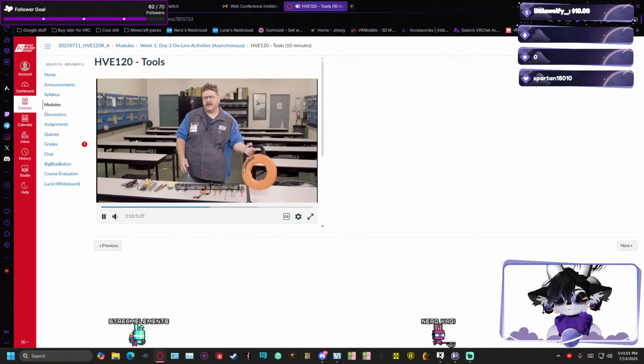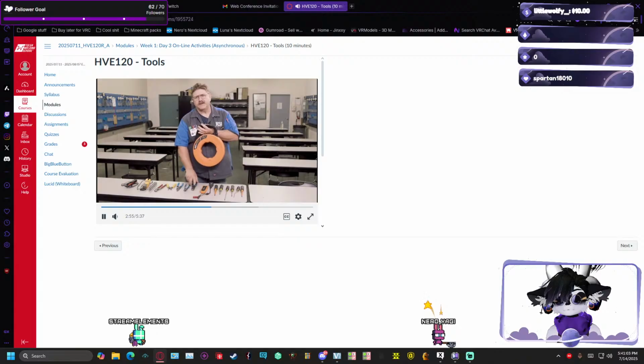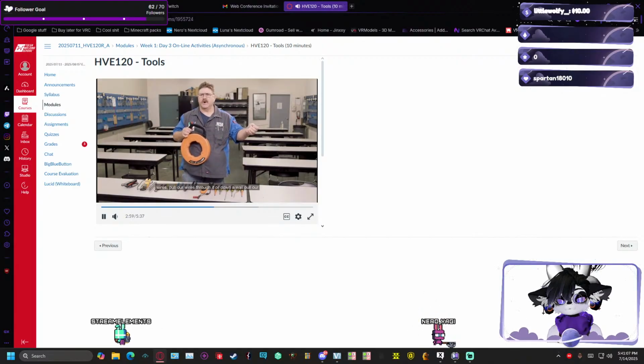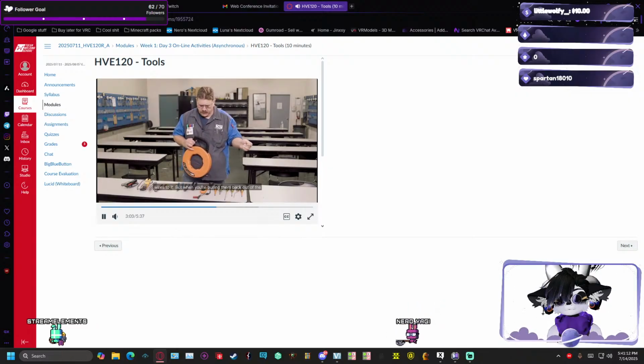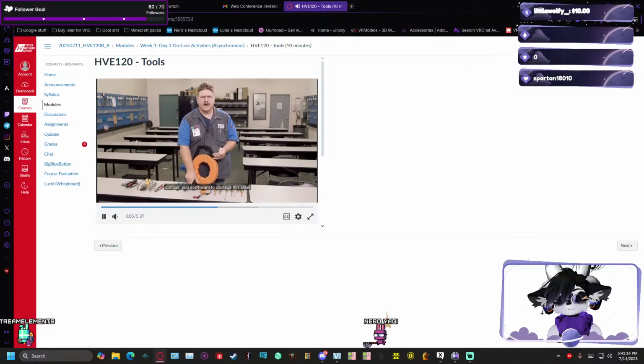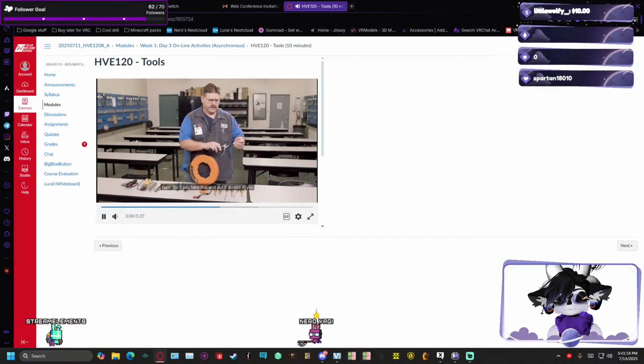Step over here to this other tool. This is a fish tape. We use these to go in our conduits to retrieve our wires, to pull our wires through it, or down a wall, pull our wires to it. But when you're pulling them back out of the conduit, you don't want to damage this steel tape. So if you take this and put it across it, you can use this as a T-handle to pull your fish tape back out of your conduit.